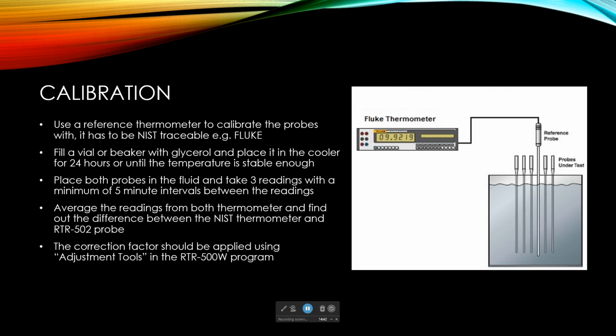After the readings are stable and don't fluctuate much, we can take 3 readings with at least 5 minutes between them, and use a calculator. First, we average the readings, then find the difference, and that difference has to be applied as a correction factor for how much it differs from the NIST thermometer. The correction factor can be applied using the adjustment tools in the RTR500W software.